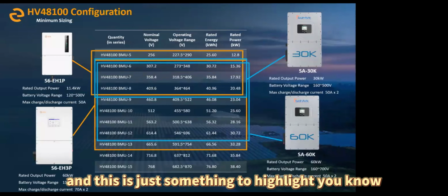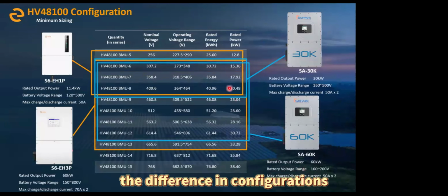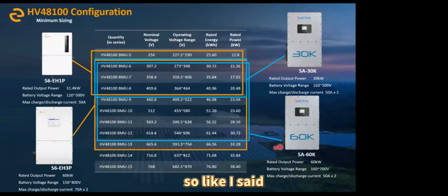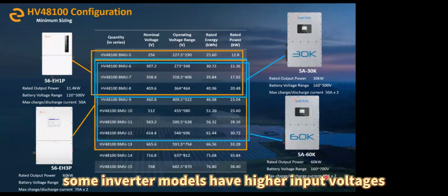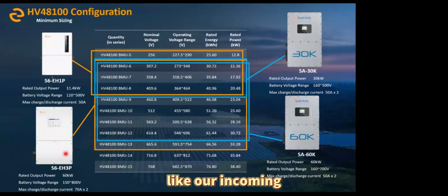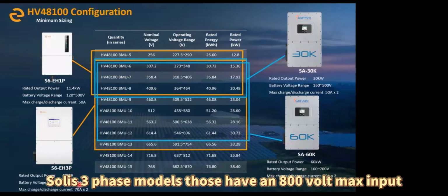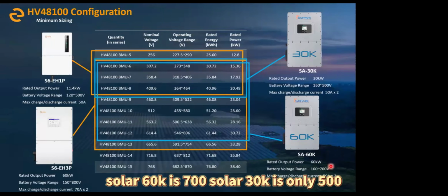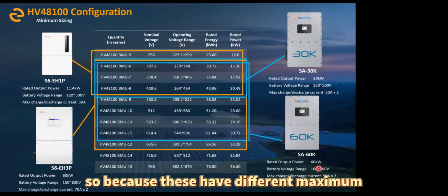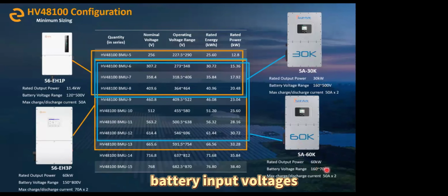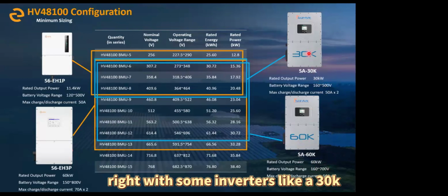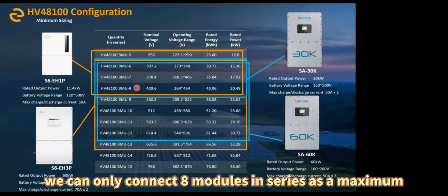This highlights the difference in configurations depending on inverter model. Some inverter models have higher input voltages, like our incoming Solis 3-phase models, which have an 800 volt max input. Sol-Ark 60K is 700, Sol-Ark 30K is only 500. Because these have different maximum battery input voltages, with some inverters like a 30K, we can only connect 8 modules in series as a maximum.